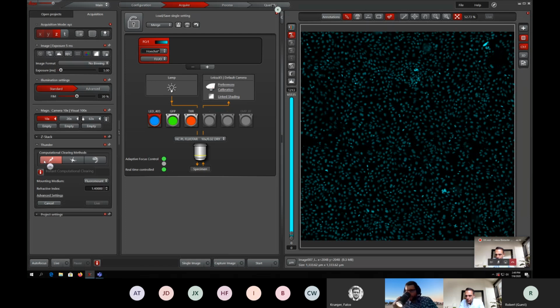If position 5 of the field diaphragm covers the entire field of view, when do you need position 6? Never. There is a difference, or why do we need even bigger sizes? The reason is the eyepieces: they have a bigger field of view than the camera chip.